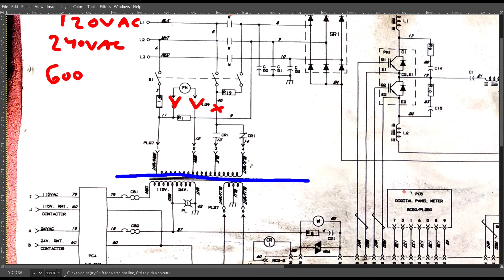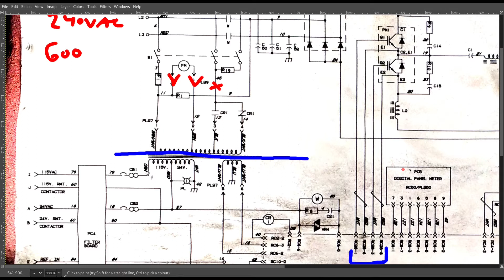Heck, you could even go on this side and hook up 24 volts AC, just as long as you make sure it's AC, or 120 to this winding here. Any of these will work for the low power section, assuming you disconnect this too, either on this side or the other one.